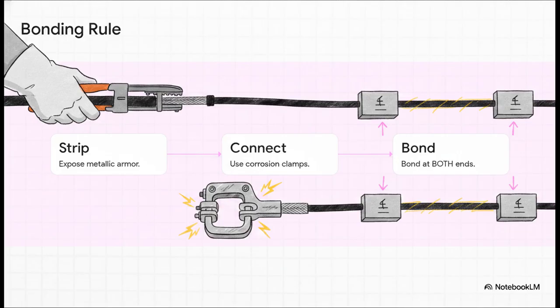Step 1. Technicians must properly strip the outer sheath to expose that metallic armor. Step 2. Connect that armor directly to an earth terminal using specific corrosion-resistant clamps, no standard solder here. And Step 3. The absolute golden rule, you have to bond it to the hull's equipotential system at both ends of the cable run. Doing this guarantees electrical continuity and completely wipes out those dangerous potential differences across the facility.